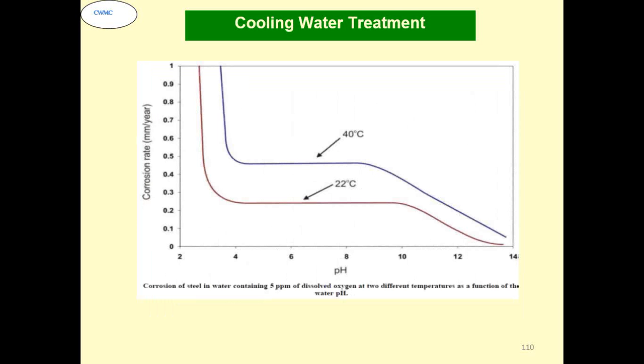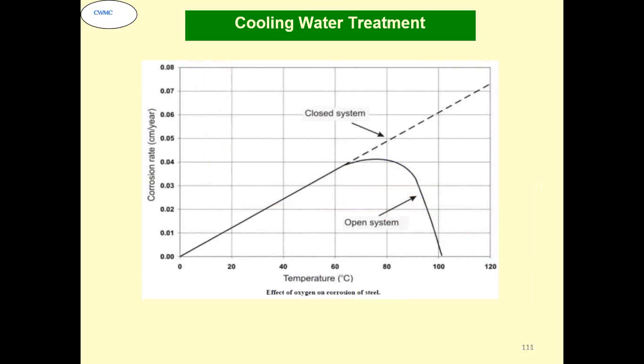Regarding the effect of oxygen also, the rate at 40 degrees or 22 degrees, as I said, almost doubles at every 10 degrees. If dissolved oxygen is present, it continues, and if it is an open system, then it starts dropping, because the oxygen will form a corrosion product which reduces the effect of the corrosion there.